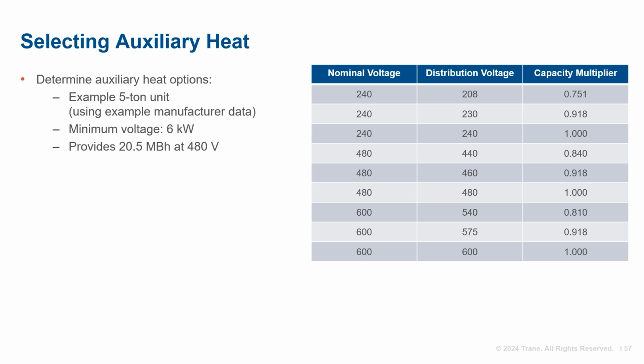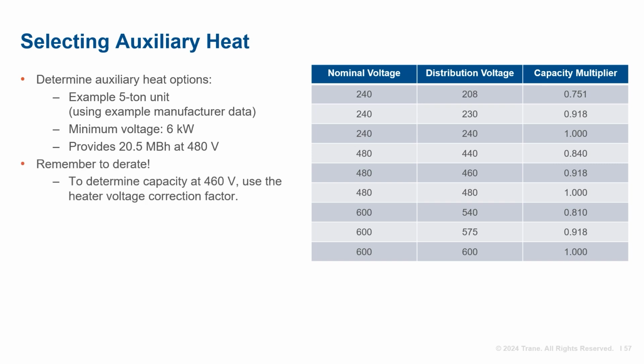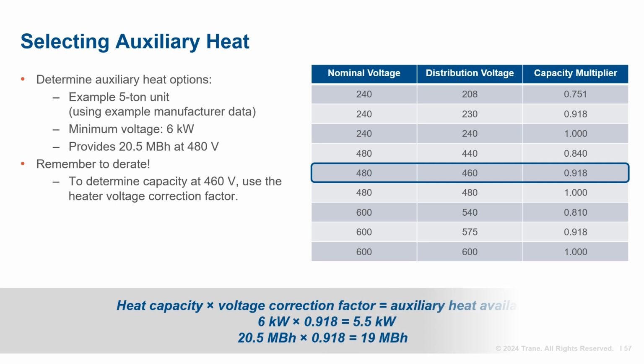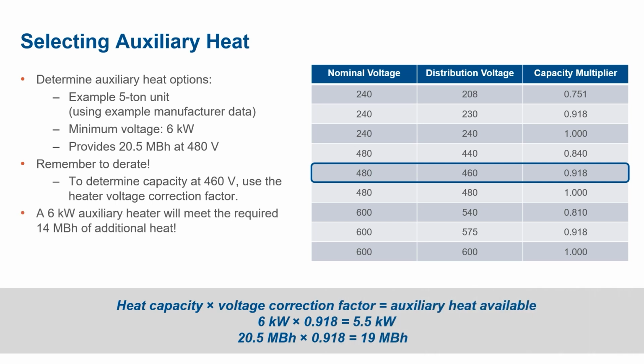This example 5-ton unit has a 6 kW minimum option, which provides 20.5 MBH of heat at 480 volts. It's important to remember to derate the auxiliary heater output based on the job site voltage. Since our example job site voltage is only 460 volts, the 6 kW electric heater will need to derate to 5.5 kW or 19 MBH based on the data from the correction factor table shown. The available 19 MBH of heat will still satisfy the required 14 MBH of auxiliary heat.